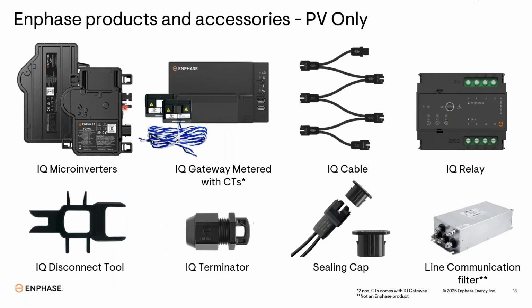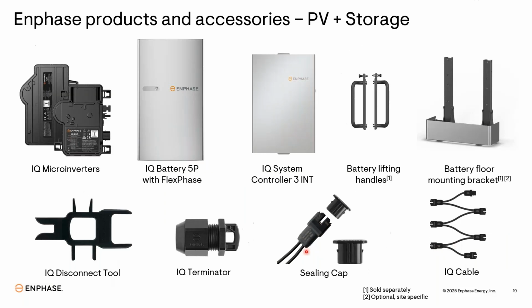If you are only going with PV systems, these are the accessories you are going to need. You need microinverters, a gateway with CTs, cables, relays, disconnect tools, terminator caps, sealing caps, and a line communication filter if required. But if you are going with storage systems, PV plus storage, you need microinverters for your panels, your battery, and the IQ system controller. These are the battery lifting handles. This is a one-time purchase only. If you want to mount your battery on the floor, you can use floor mounting brackets. This is the disconnect tool. This is the terminator cap, sealing cap, and IQ cables. So these products you need there.